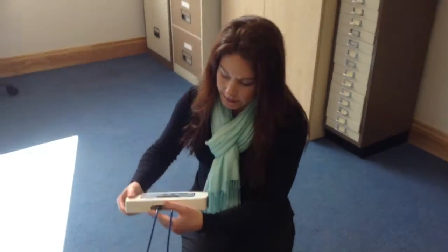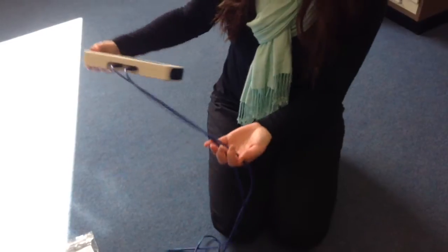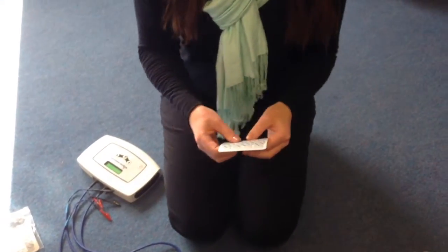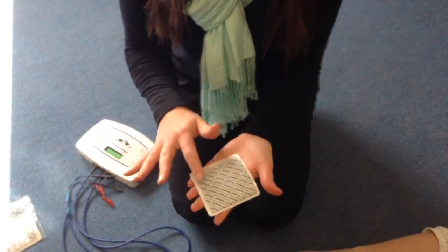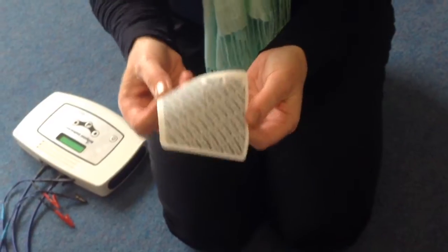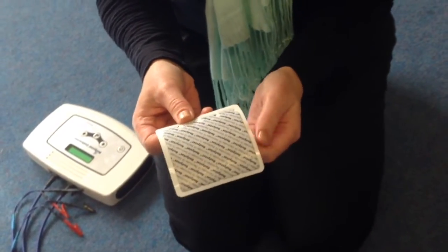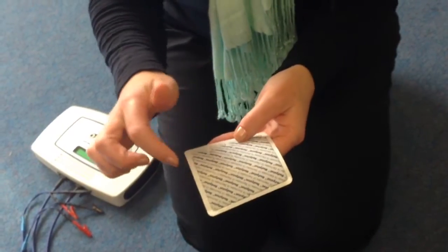The first thing you do is connect the lead wires securely to the unit. Make sure they're fit securely and not loose, and we fit the electrodes to the person. For the Quad Scan and for the MDD there are four long electrodes per strip. For each test you need four electrodes, and for the 1500 you also need four electrodes but the electrodes are a lot smaller.